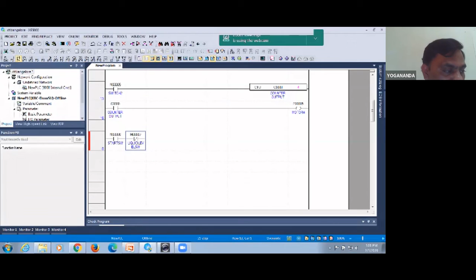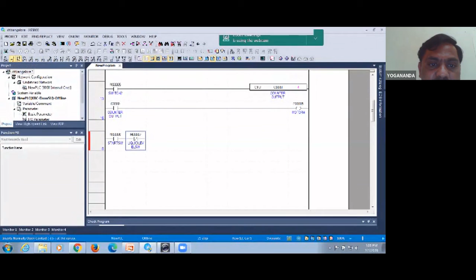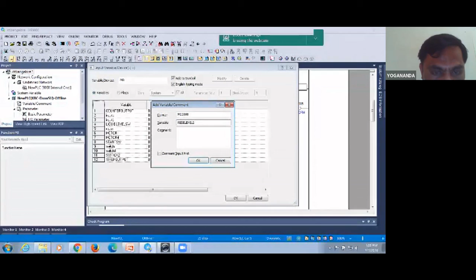Next, one more switch. There should be sufficient liquid in the reservoir, meaning it is full. Full means it is always high. For that reason, I am going to select a normally open contact switch, with M8 as the device name. So I am going to check the reservoir level switch. So it is normally open now.